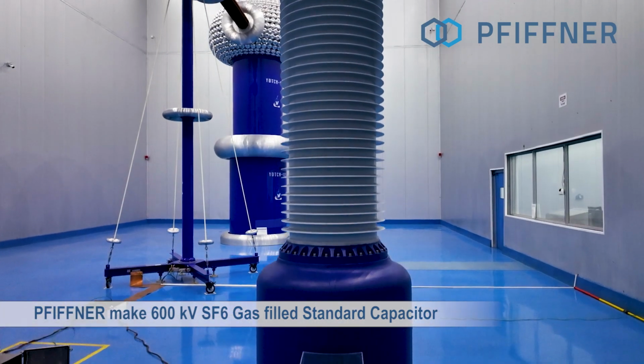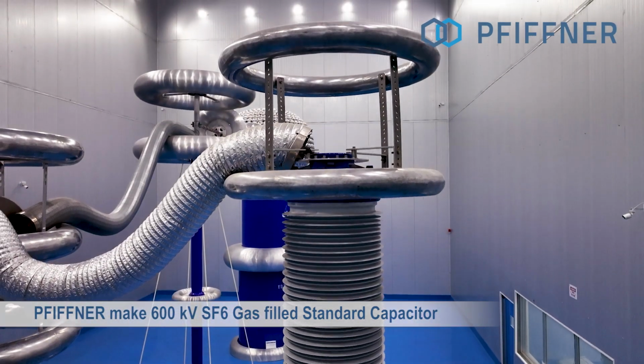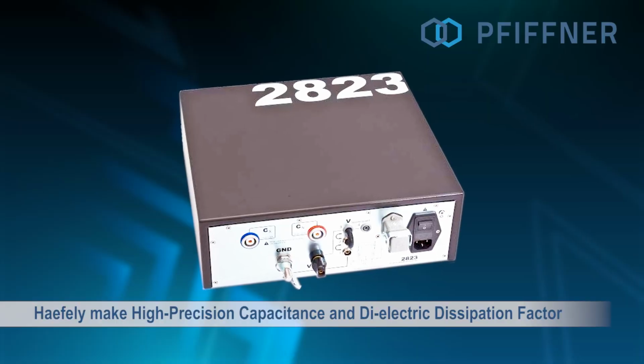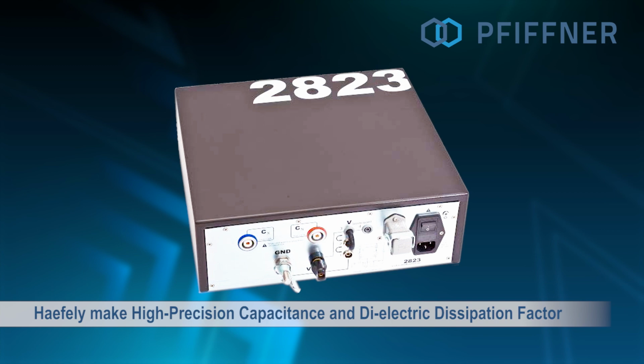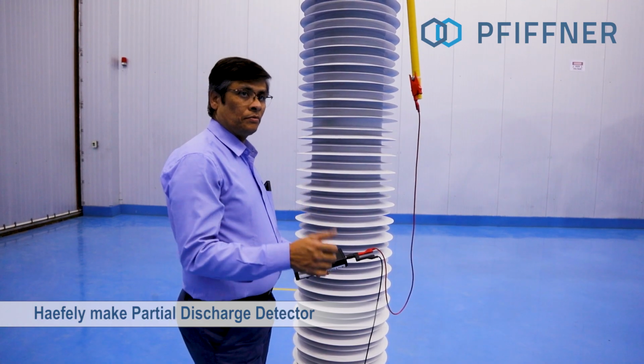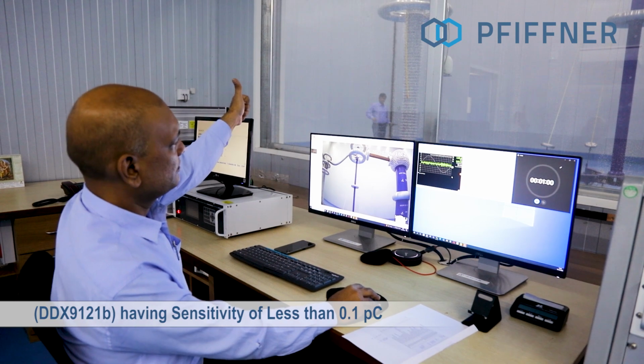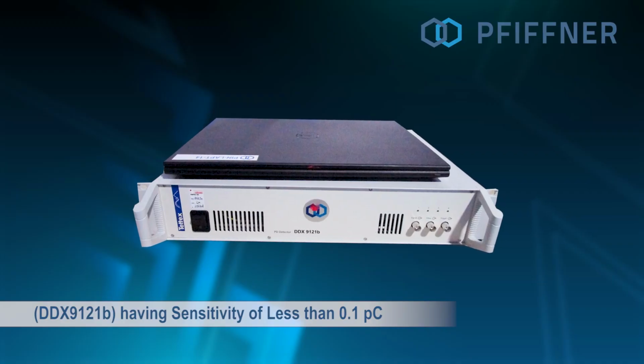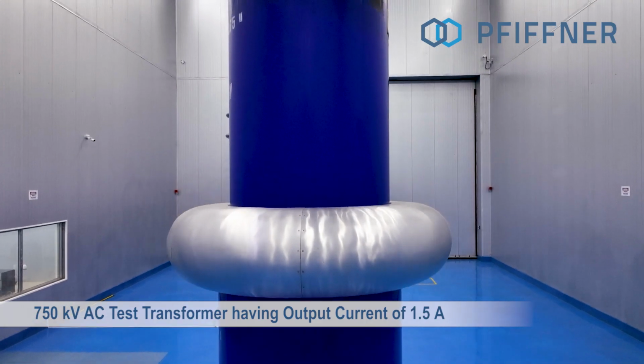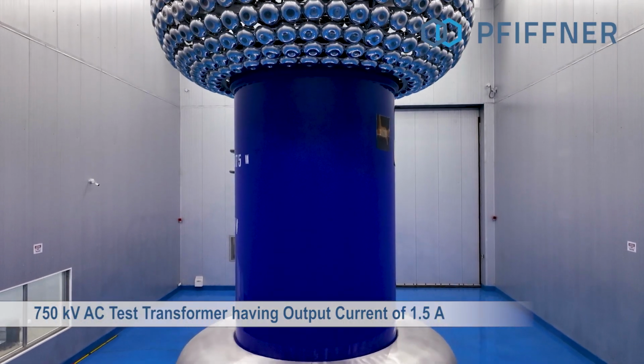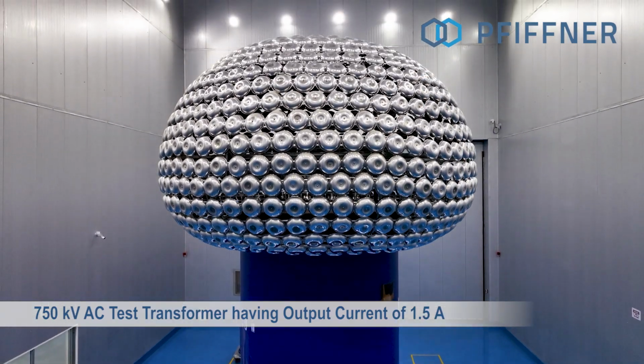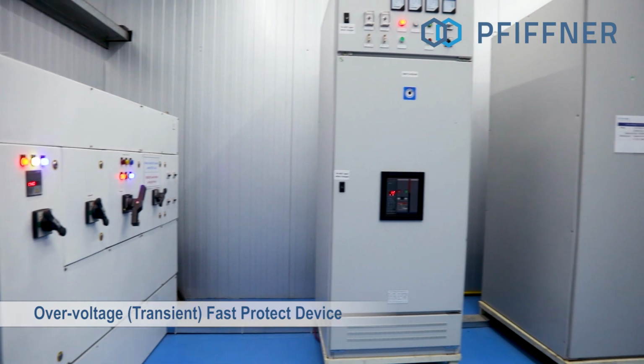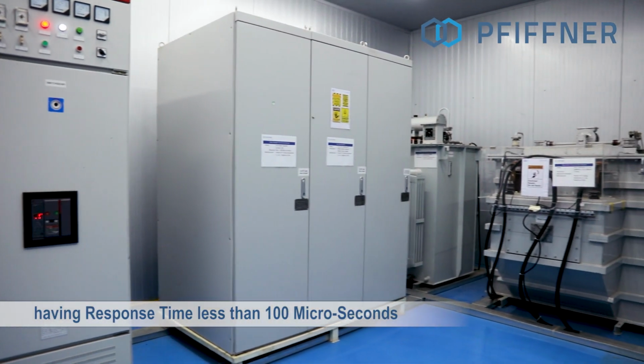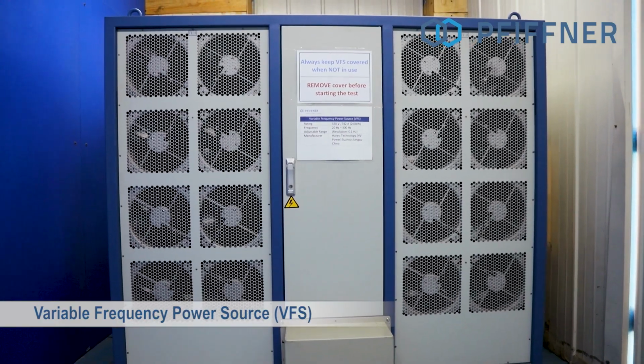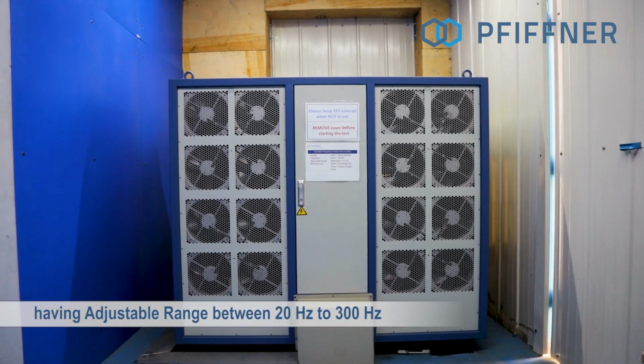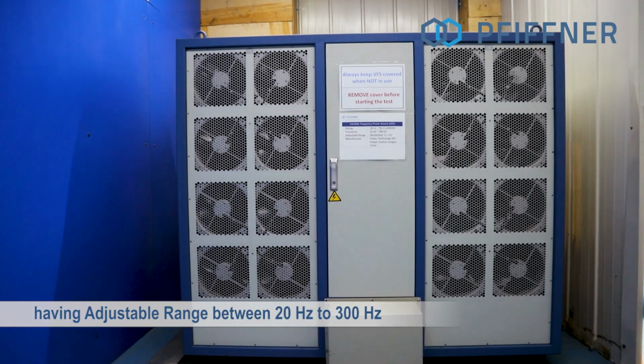Pfiffner make 600 kV SF6 gas-filled standard capacitor. Haefely make high precision capacitance and dielectric dissipation factor measuring system. Haefely make partial discharge detector DDX9121B, having sensitivity of less than 0.1 pC. 750 kV AC test transformer having output current of 1.5 ampere. Overvoltage transient fast protect device having response time less than 100 microseconds. Variable frequency power source, VFS, having adjustable range between 20 Hz to 300 Hz.